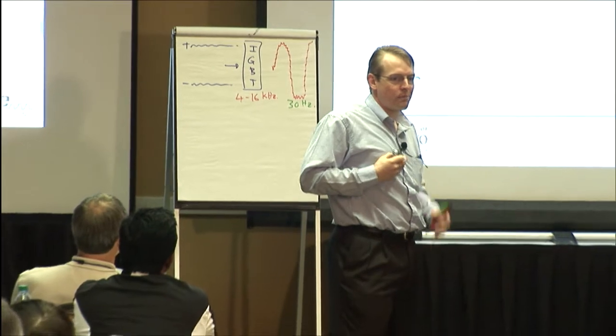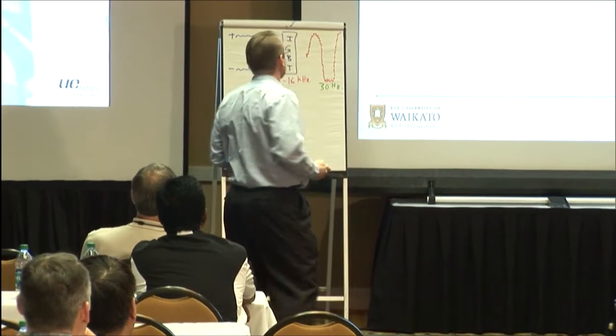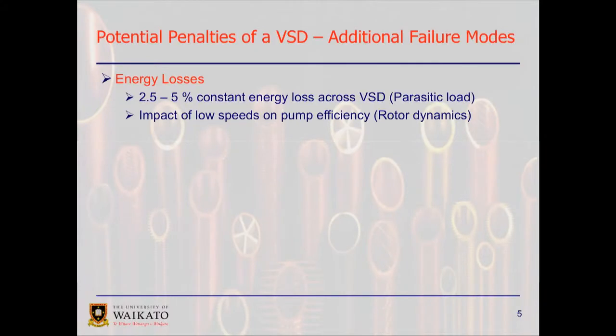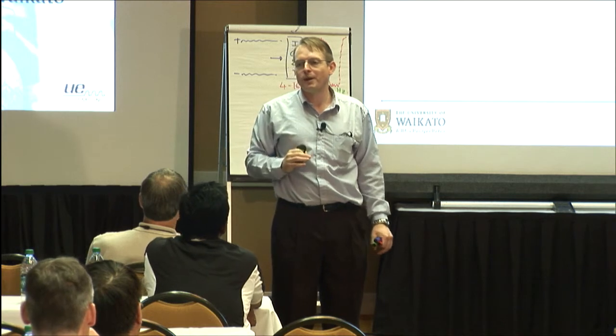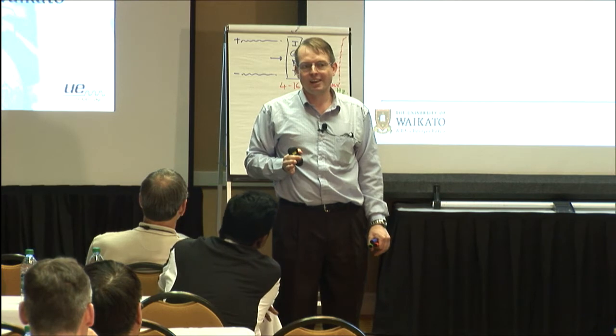Can you see a bit of a paradox here? So you kind of have to be a little careful. Okay, number one though, is the minute you put that VSD in, from day one till day infinity, you are giving up somewhere between 2.5% and 5% of your power consumption continuously. Okay, how do I know that?